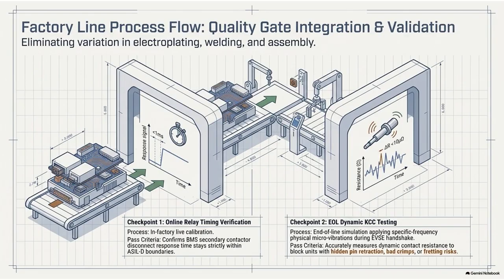Why wouldn't they open fast enough? If the software sends the signal instantly, what slows down the relay? Mechanical reality. A contactor is a heavy electromagnetic switch. It uses a magnetic coil to pull a heavy metal armature against a heavy spring.